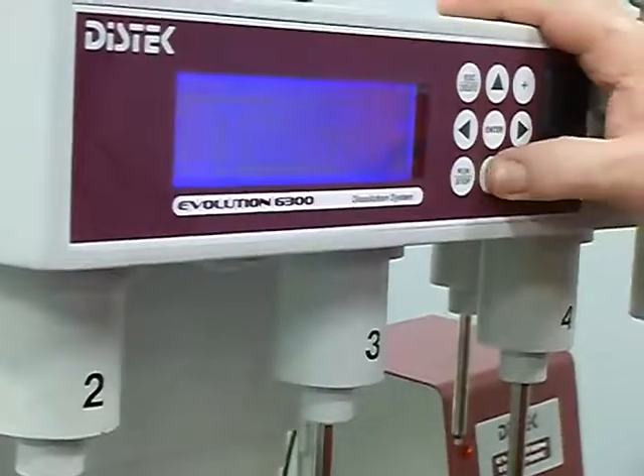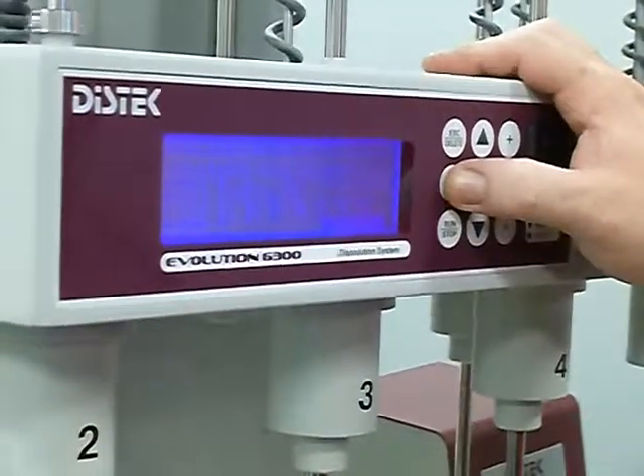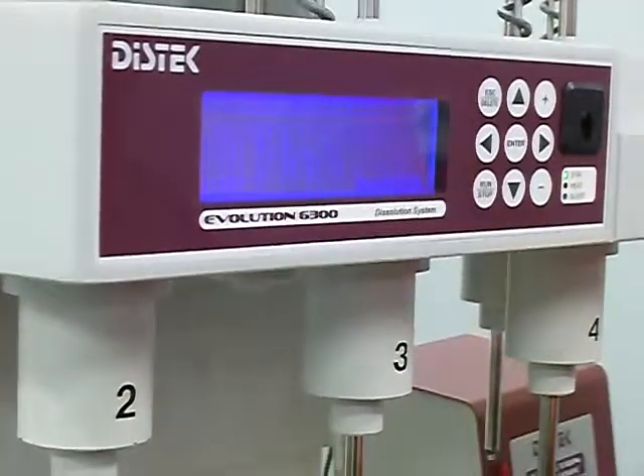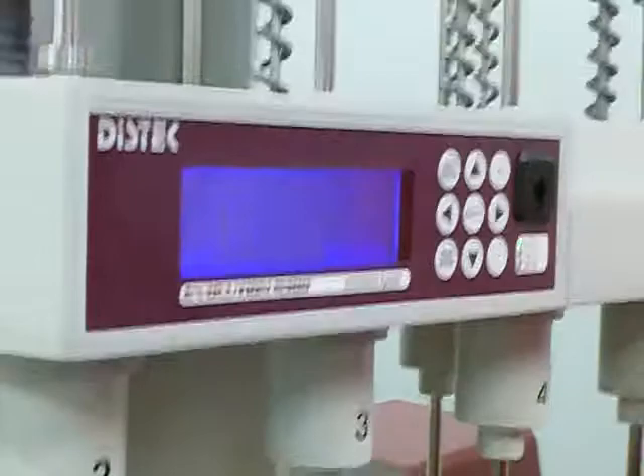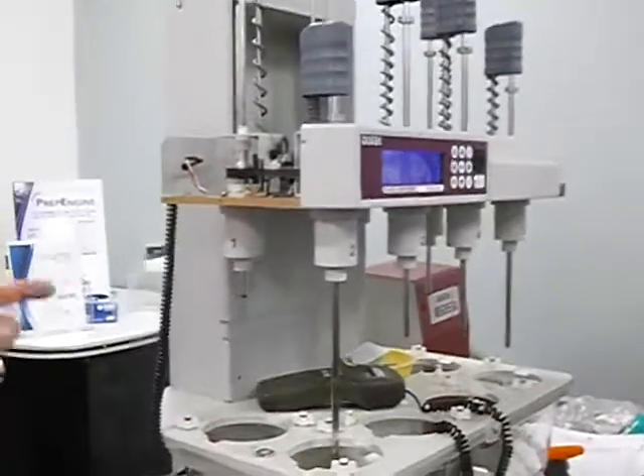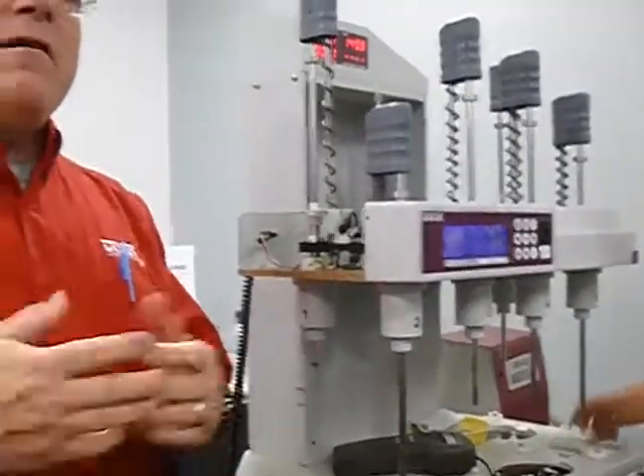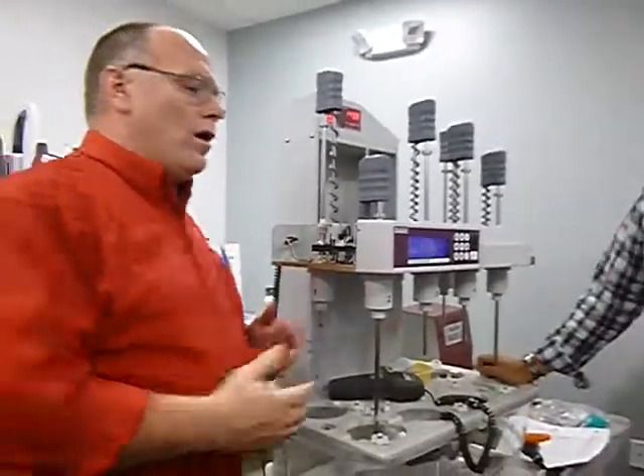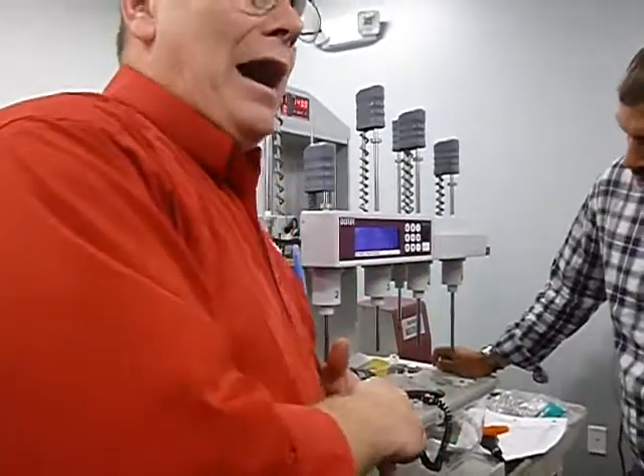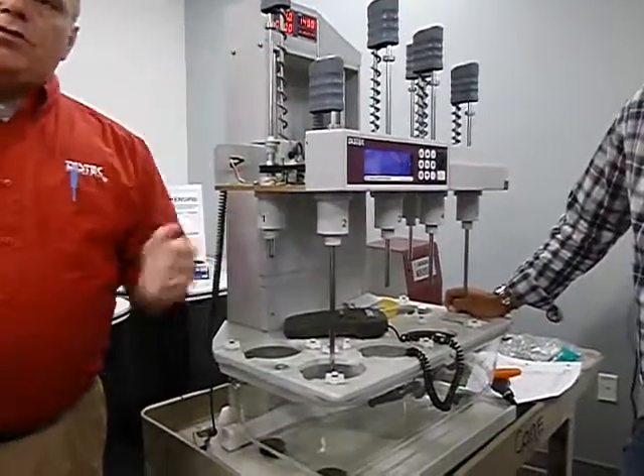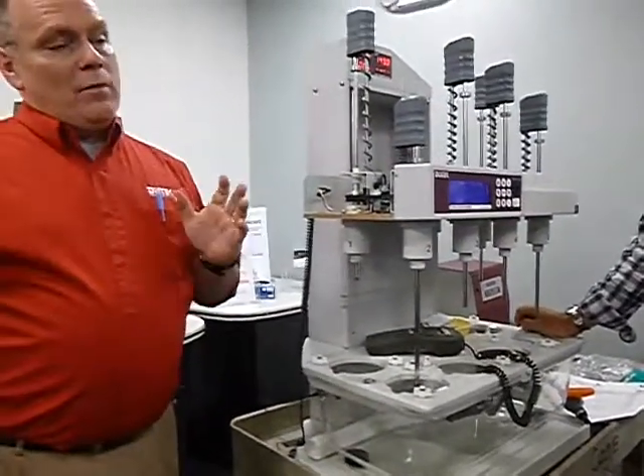The screen upper is the same, right? Pardon? There is no low screen calibration. No, it automatically detects. Yeah. It detects a difference of 15 degrees. So what it means is if you were to do a low calibration at 23 degrees Celsius, as long as you did the upper one 15 degrees warmer than that, it'll automatically detect and put you into the higher calibration screen. Okay. It automatically defaults to high or low. It knows already. You want to try and get below 20 degrees Celsius, and you want to try to get to around 40 degrees Celsius.